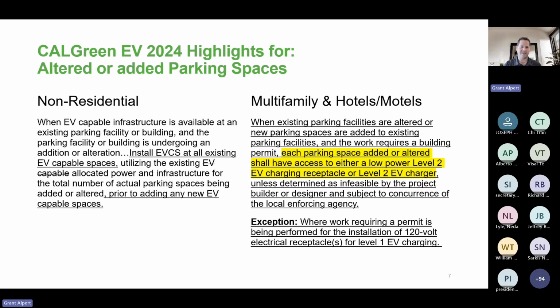I'll continue on to the highlights for altered or added parking spaces. On the non-residential side, there was a possibility that when a non-residential building was adding EV charging stations, they would bypass whatever existing allocated power and infrastructure were already there, and just trench new holes, add new conduit, new cable, and install the EV charging there. This code change basically says if there's already allocated power and infrastructure for EV capable spaces, that has to be used before you add new EV capable spaces. It's kind of closing a loophole that prevented more EV charging from being installed.